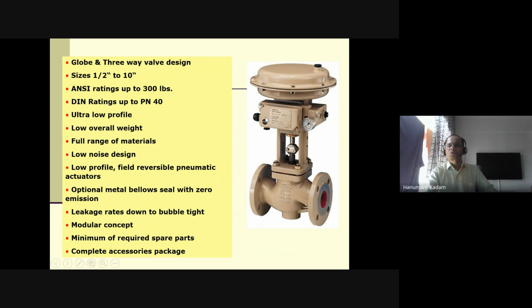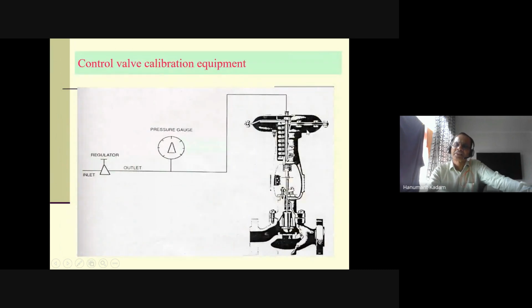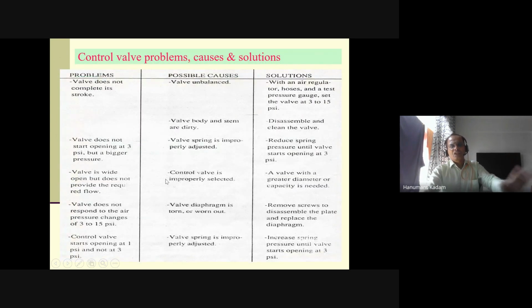So this is the positioner, and you can see the air supply is required. Here indicators are there. Control calibration, if you see here, the positioner is attached here. Control valve problems, causes, and solutions we'll see later on. First, we'll discuss the positioners.